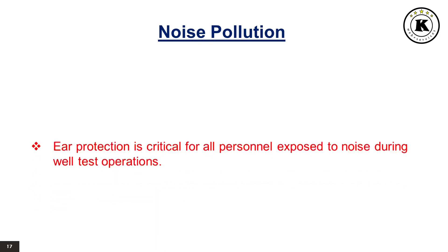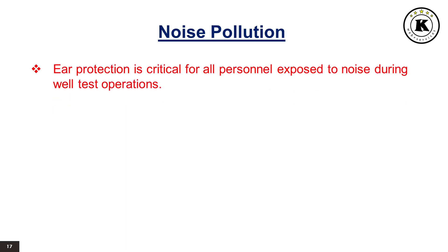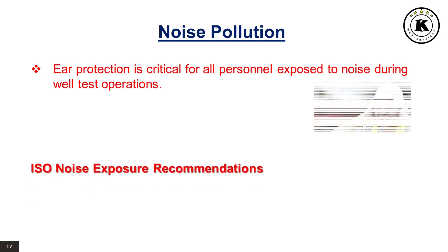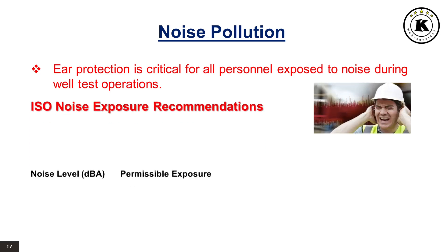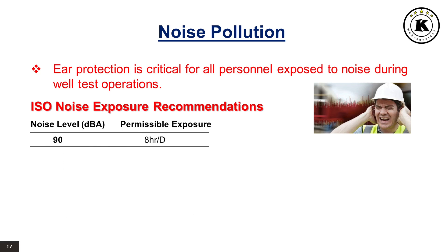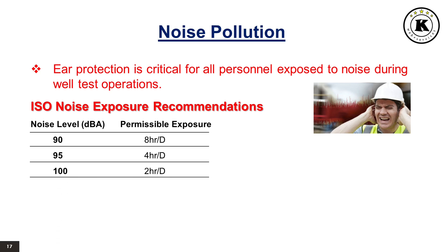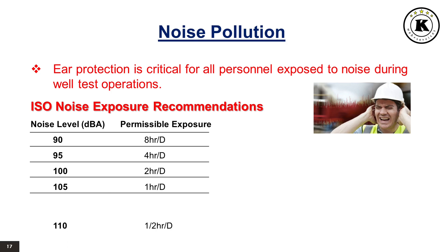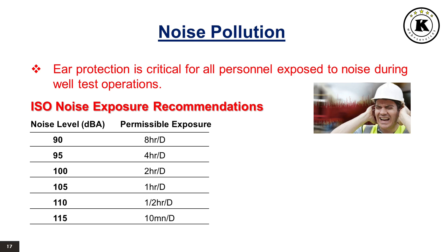Noise pollution: Ear protection is critical for all personnel exposed to noise during well test operations. According to ISO noise exposure recommendations: at 90 dB, permissible exposure is 8 hours per day; at 95 dB, 4 hours per day; at 100 dB, 2 hours per day; at 105 dB, 1 hour per day; at 110 dB, half an hour per day; at 115 dB, 10 minutes per day.